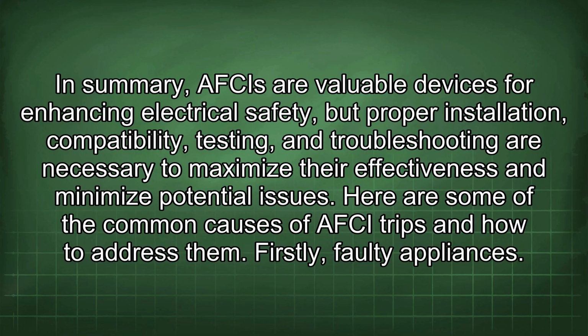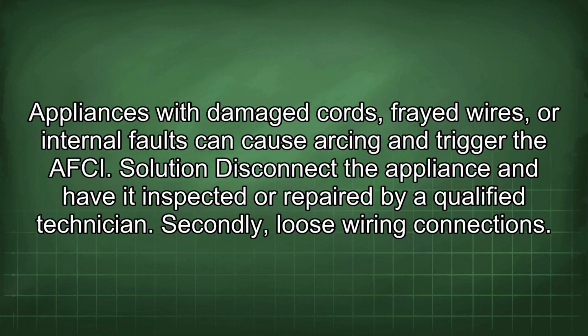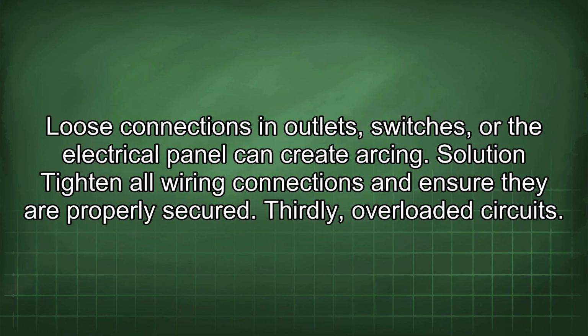Here are some of the common causes of AFCI trips and how to address them. Firstly, faulty appliances. Appliances with damaged cords, frayed wires, or internal faults can cause arcing and trigger the AFCI. Solution: disconnect the appliance and have it inspected or repaired by a qualified technician. Secondly, loose wiring connections. Loose connections in outlets, switches, or the electrical panel can create arcing. Solution: tighten all wiring connections and ensure they are properly secured.